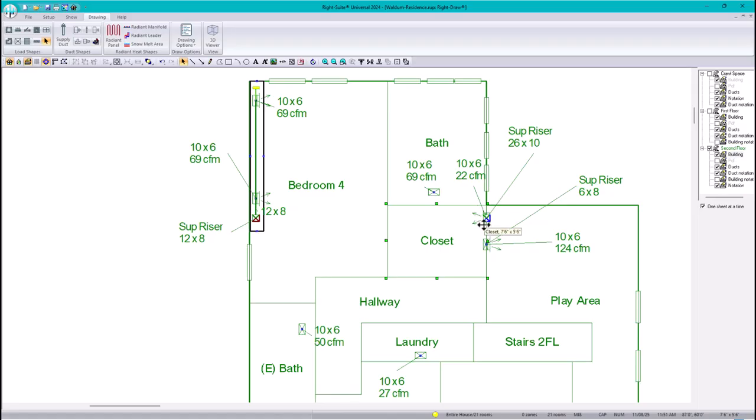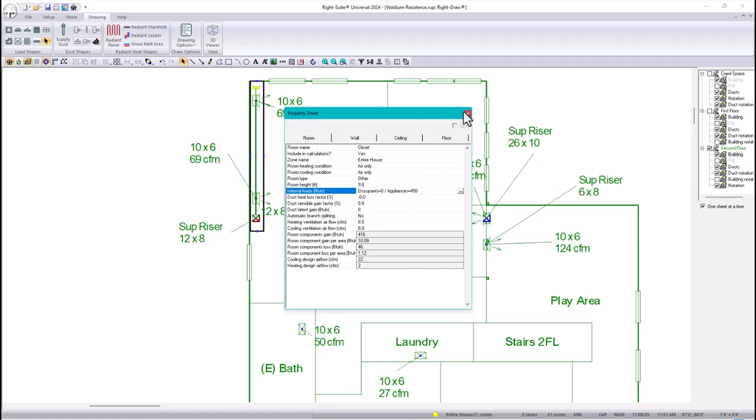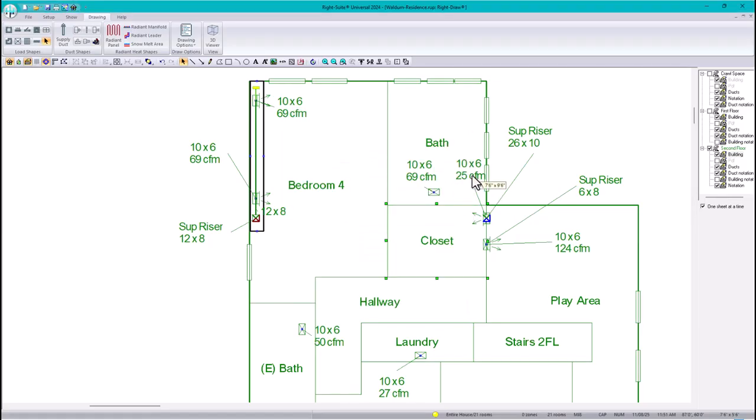Depending on the manufacturer, depending on the home builder, sometimes they have a minimum requirement. Sometimes they say 20 CFM at least, this is the minimum. Other ones say 30 CFM. In commercial, we have 30 CFM minimum for ventilation. But the federal government in the United States has a minimum requirement of 50 CFM. So we can leave it at 22 CFM, or we can make it a little bit bigger, say 450. So let's try. This is 25 CFM, so that way it's more manageable, right?